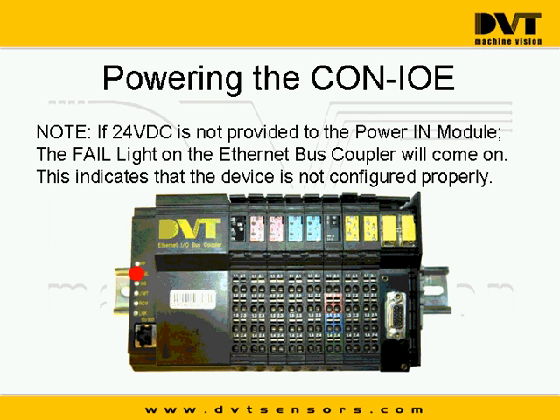Now, the other thing that you also want to make sure you keep your eye on is the LEDs on the far left side of this DVT Ethernet coupler. There is one particular light there that monitors pretty much anything that could possibly go wrong when it comes to making a power connection, making a camera connection, and making communication happen properly throughout the system. It is an LED labeled fail. It will either flash red with a certain frequency, or it will just go high and show red, showing you that there is a problem with the connection or with some power.